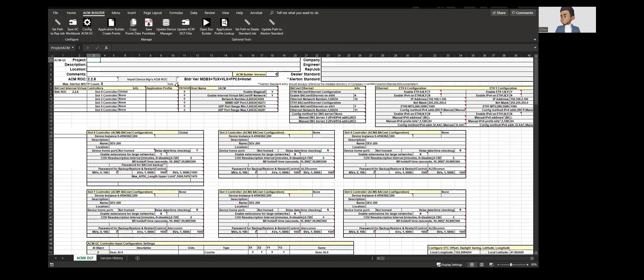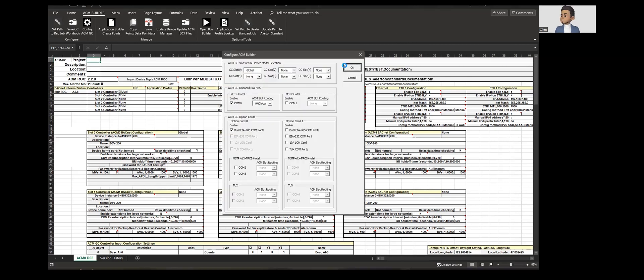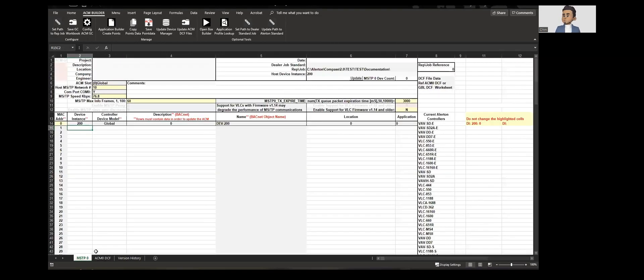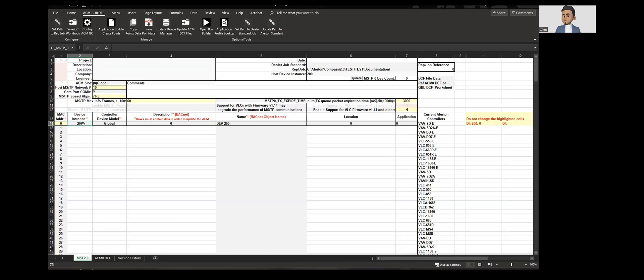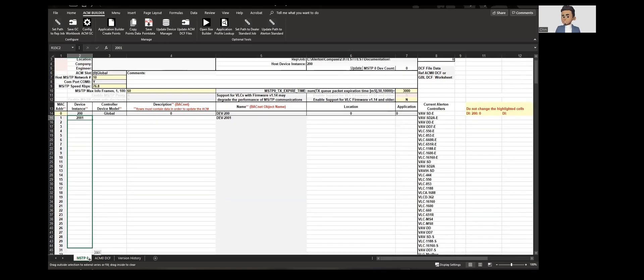This is the ACM builder file. Let's create a global file. I will not go through all the details here. Please comment me in the comment section if you would like a detail video on how to configure this. I used to use this in day-to-day job where I used to keep the IP address handy and all the device settings ready. We'll click okay. We see an MSTP device has been created. We will call this device 2001 and then let's say we want to add 32 devices.